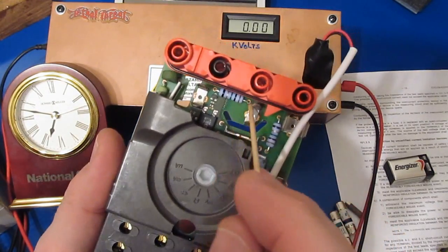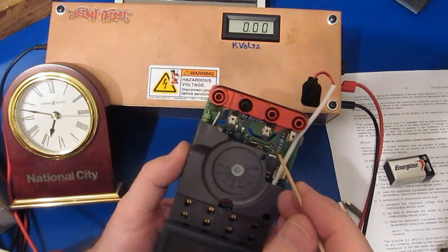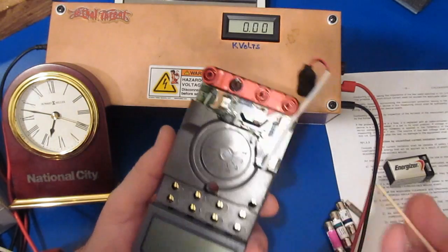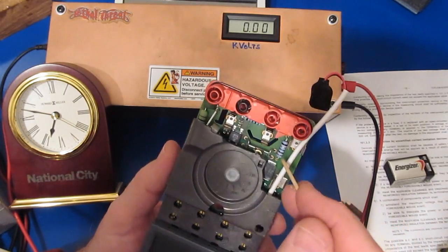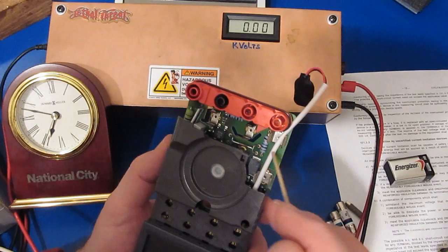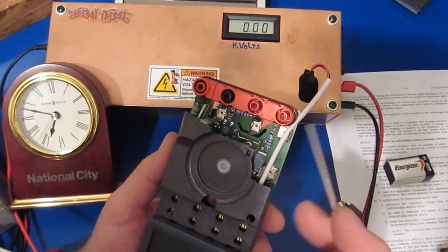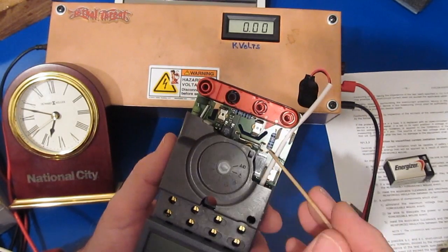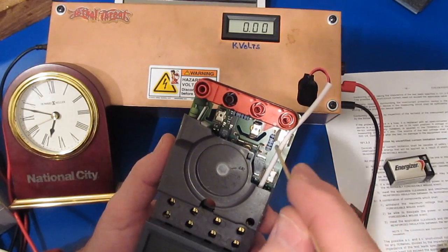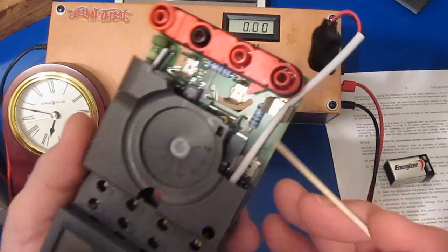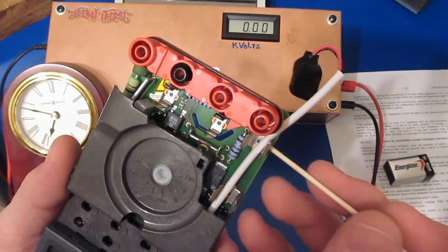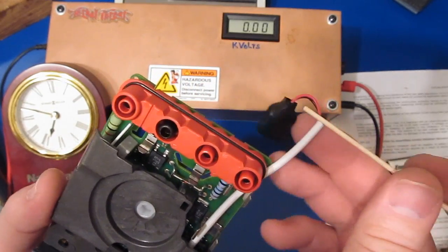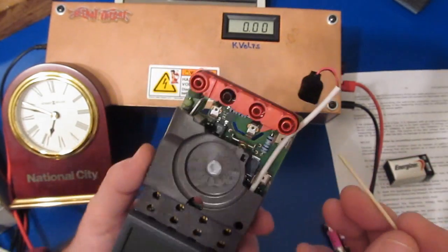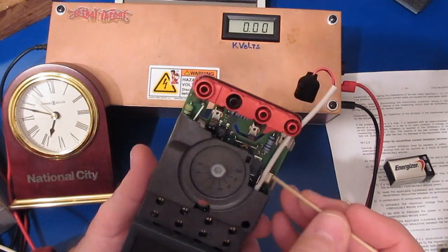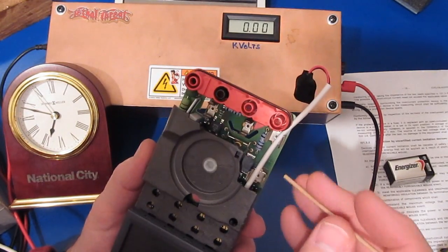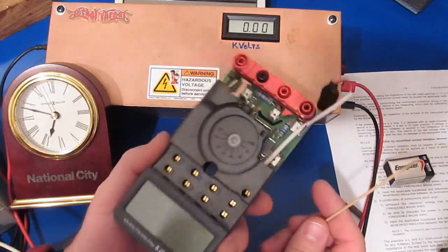Of course, that's only going to be for 1 minute, as the test calls for. I assume it's fine, or the meter wouldn't have been certified. I am sort of amazed they're not using a higher value than this. I'd like to pull that resistor out and repeat the test, because I'm still concerned about it breaking down through this sheath into the wiring here. But I just don't have a way to conduct that test right now - I'd need a bigger power supply than what I have available.